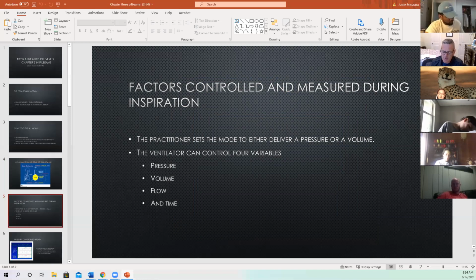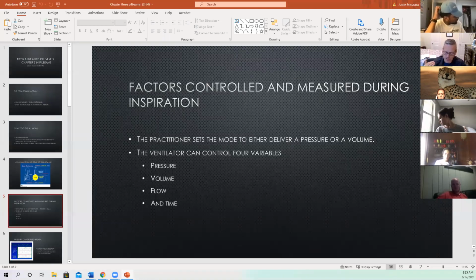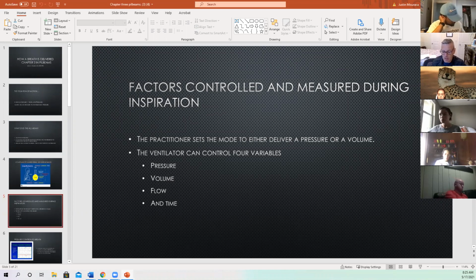When we're looking at a ventilator, we typically have two major mode categories that we use. This is where we get people's minds stuck in this weird loss of knowledge, right? You have categories of modes. You have pressure modes, volume modes, and then flow and time, which you almost never see anymore. It's good to know they exist. But pressure modes and volume modes are the two categories. You have an SIMV pressure mode, an assist control pressure mode, and then you have an SIMV volume mode and an assist control volume mode. So there's those two major categories, pressure and volume.